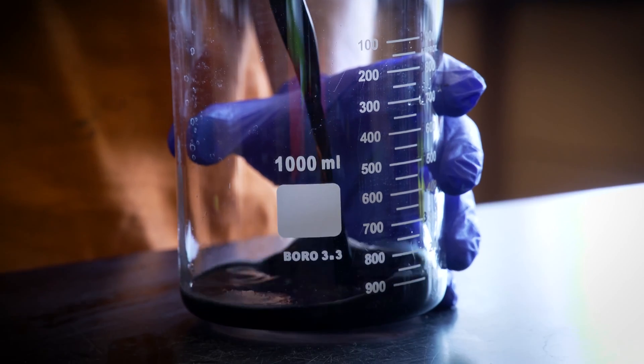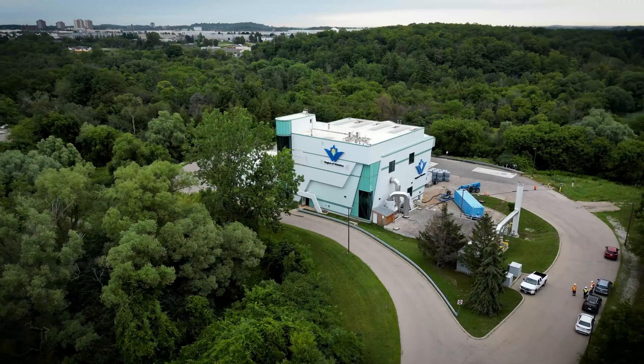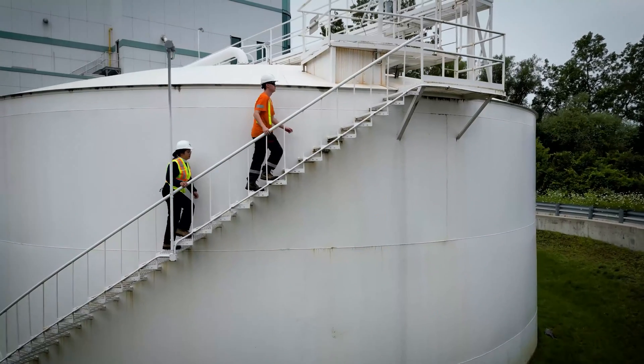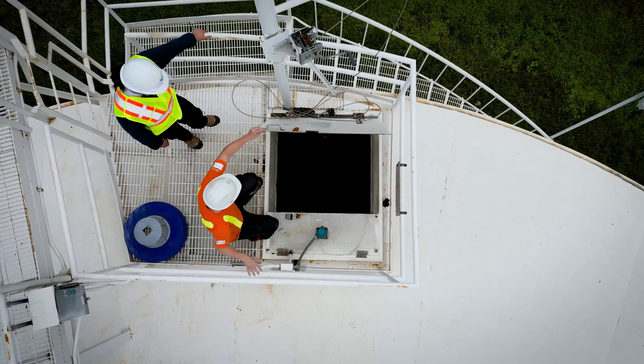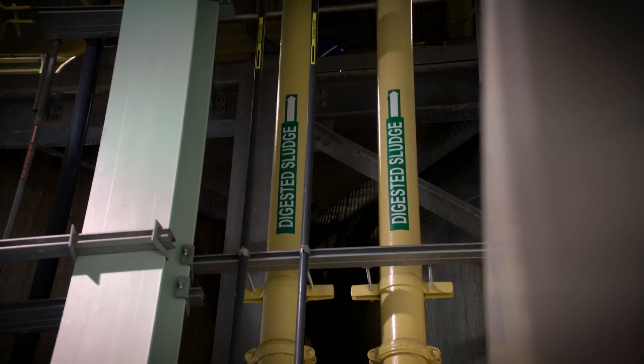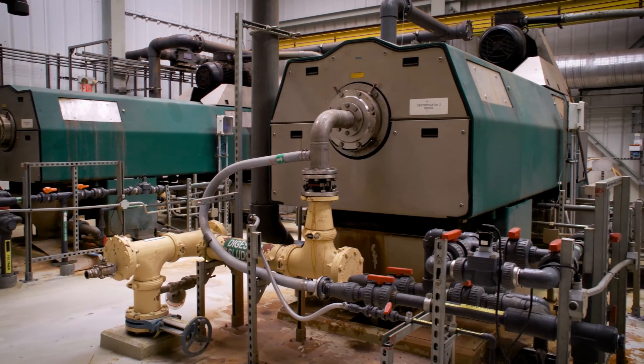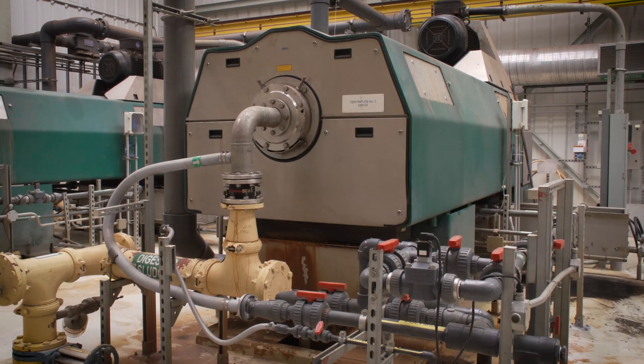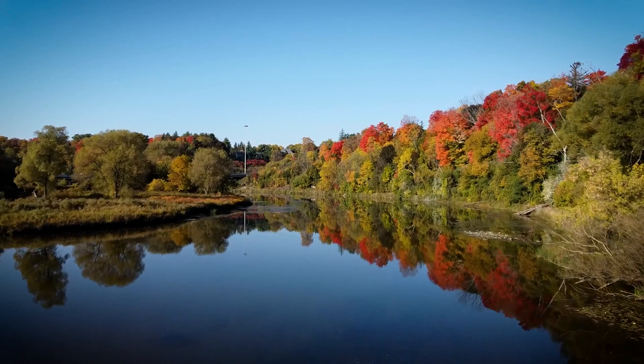The solids are now a soupy mixture we call sludge. Transporting the sludge to its final destination would require many trucks, so instead we pump the sludge through a pipe to a dewatering plant on Manitou Drive in Kitchener. When the sludge arrives at the plant, it is temporarily stored in a holding tank that can hold approximately 1 million litres and is emptied daily during the weekdays. The sludge is then pumped through pipes to a centrifuge for dewatering. The centrifuge uses gravity and the force of speed to push the water out of the solids — think of it like a really big salad spinner. A polymer is added prior to the sludge entering the centrifuge to speed up the dewatering process. The excess water leaves the centrifuge and returns to the Kitchener Wastewater Treatment Plant to rejoin the treatment process before returning to the Grand River.